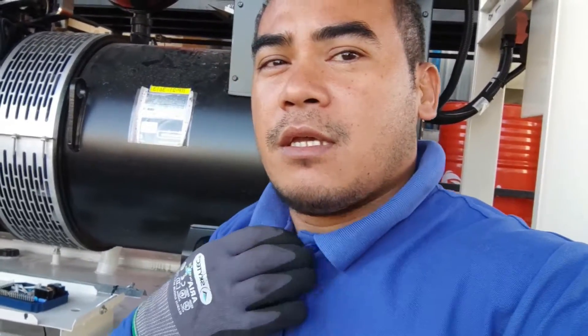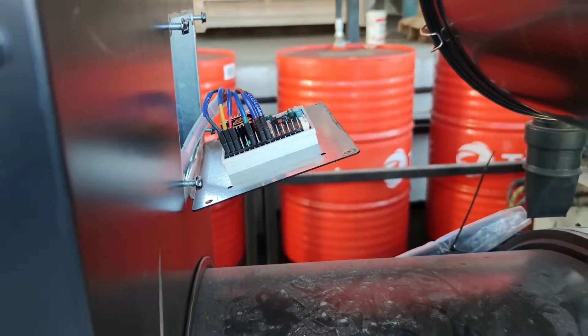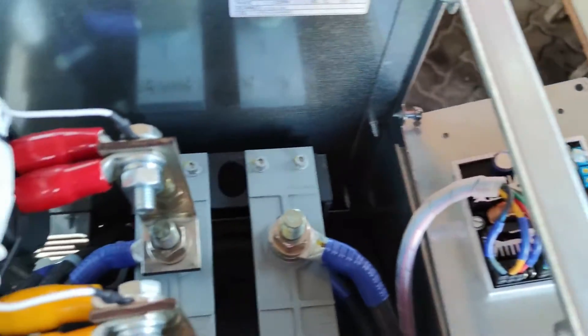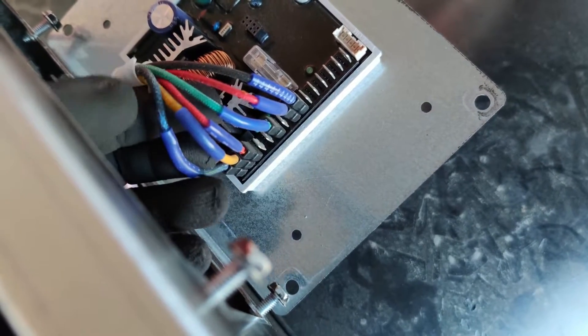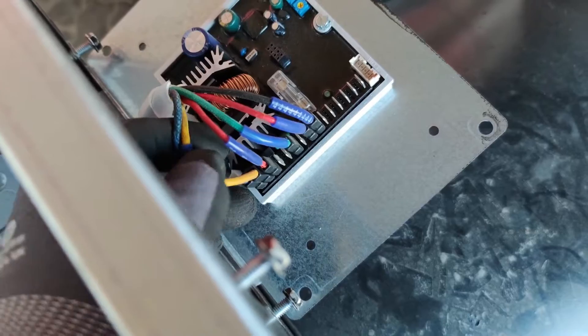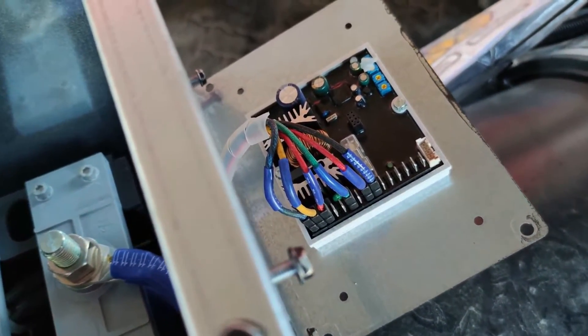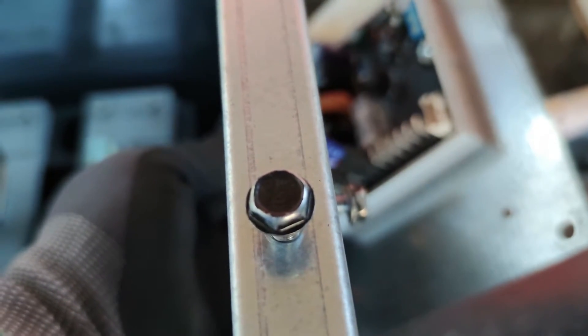I'll show you the AVR we're changing from DSR to DER1. This is the AVR installed in this Mecc Alte alternator. Here are the connections from inside — this is from our exciter, the black and yellow. This is from our sensing side. This alternator has an auxiliary winding, so the two red wires are from our auxiliary. The rest is for our sensing.